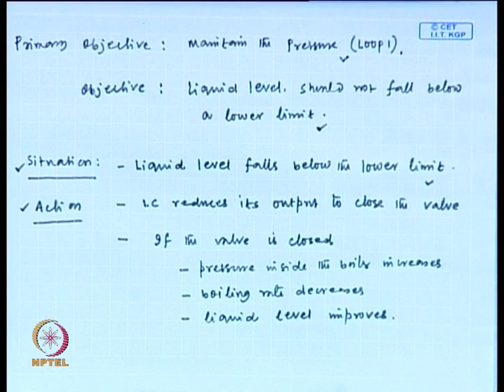So, therefore, a crucial action is required from the level controller side. So, this is a situation and the corresponding action taken by the level controller. Now, I am just trying to highlight the steps. Initially, the pressure controller or pressure control loop is in action. Then the water level falls below the allowable limit. This situation we have considered. Then the level controller reduces its output to close the valve.